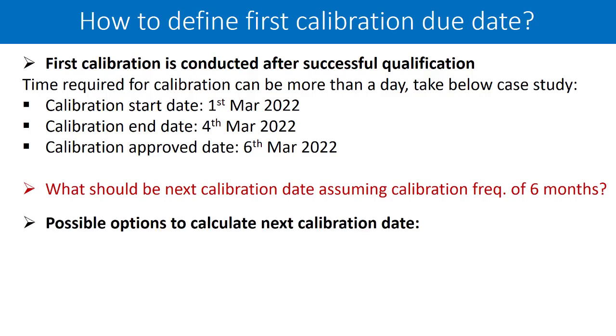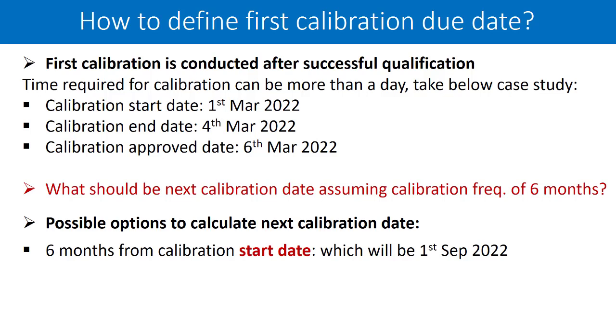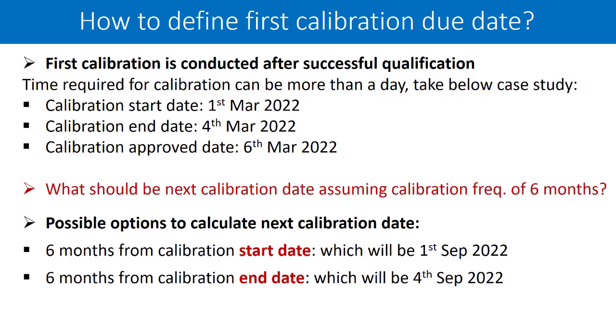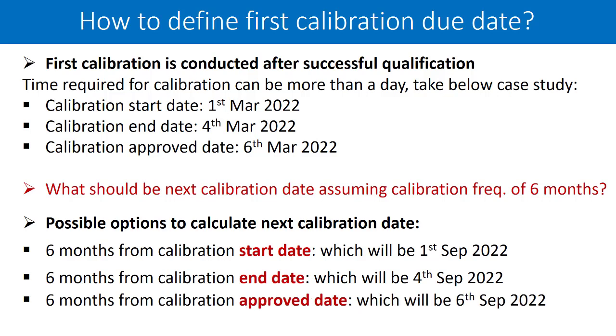You can have the following options. The first option is 6 months from the calibration start date, which will be 1st September 2022. The second option is 6 months from the calibration end date, which will be 4th September 2022. The third option is 6 months from the calibration approval date, which is 6th September 2022. I have simply calculated 6 months from each of the respective dates — start date, end date, and approved date.